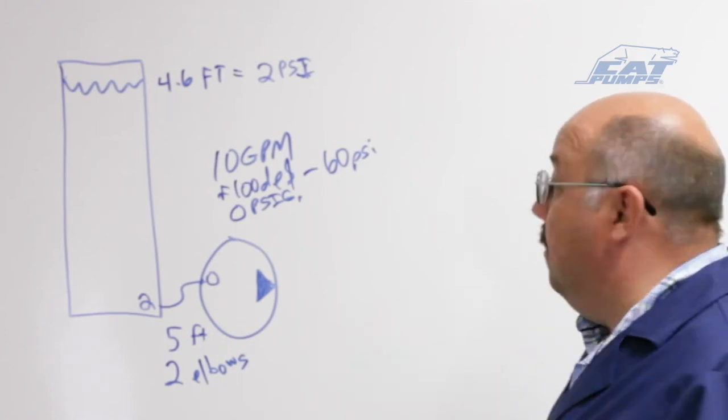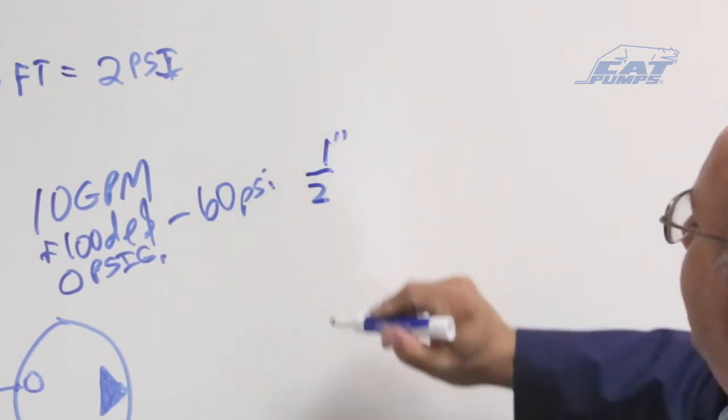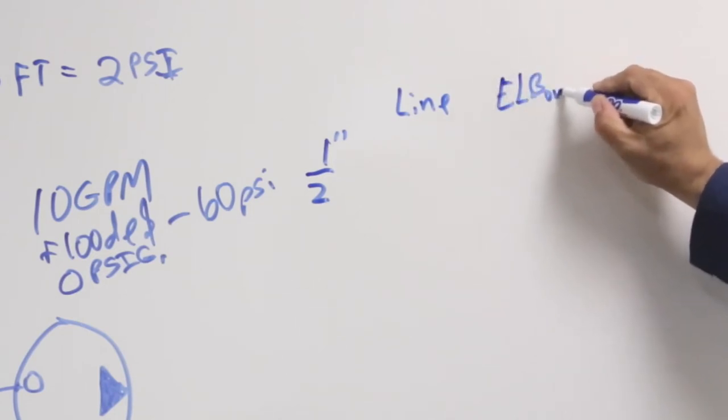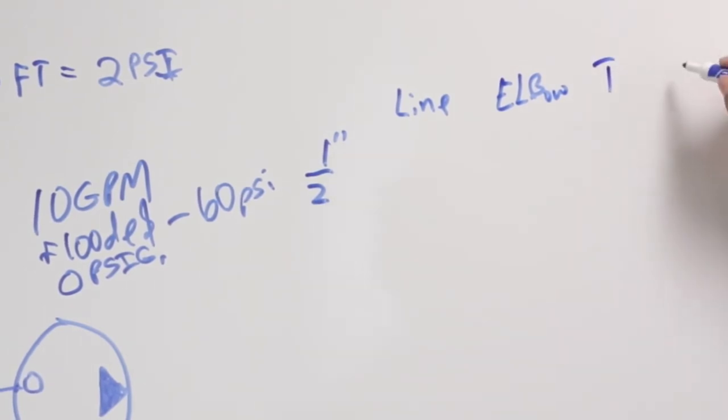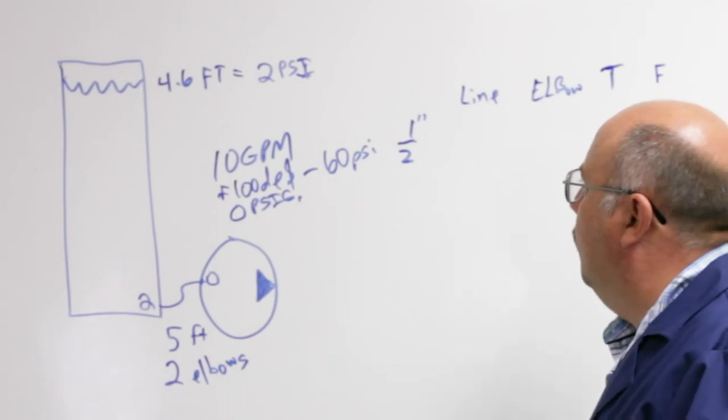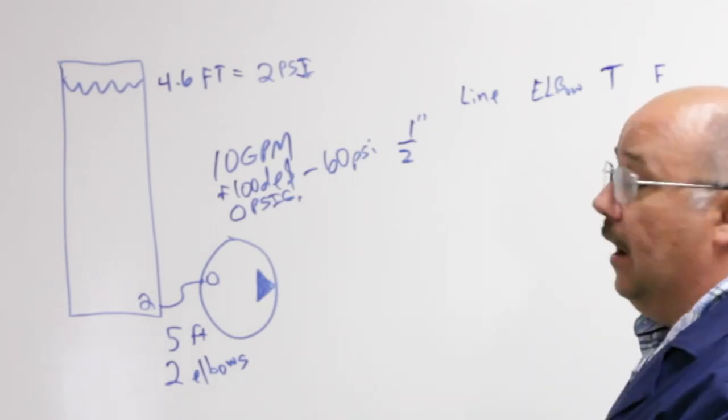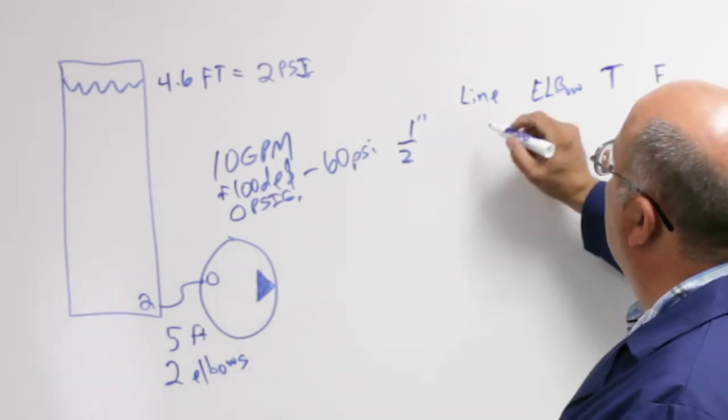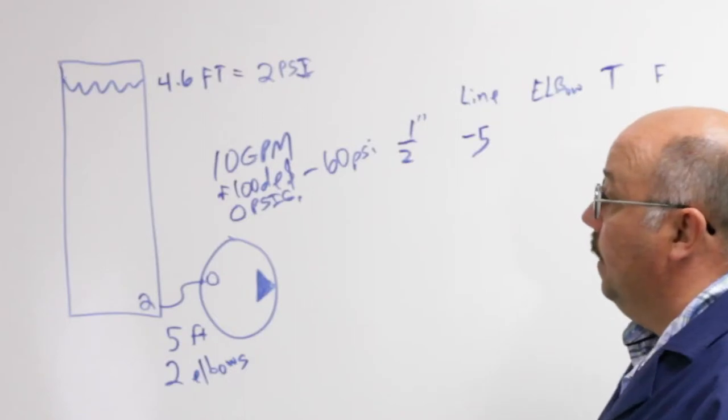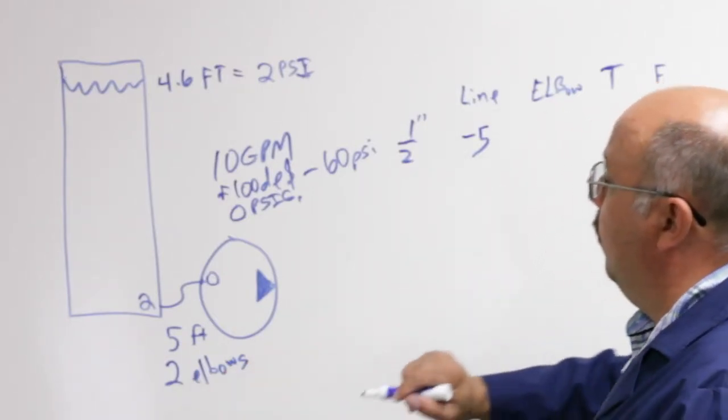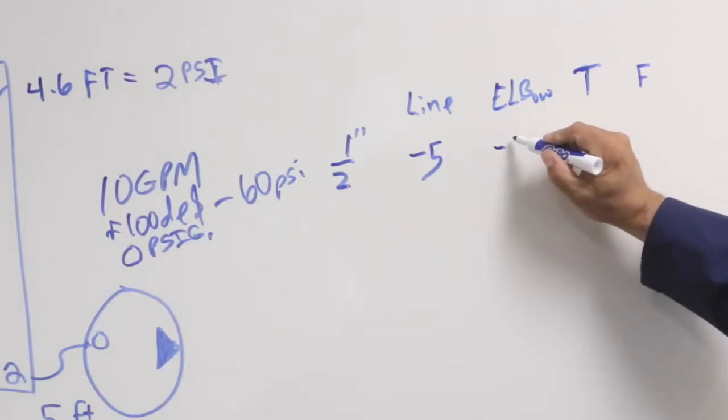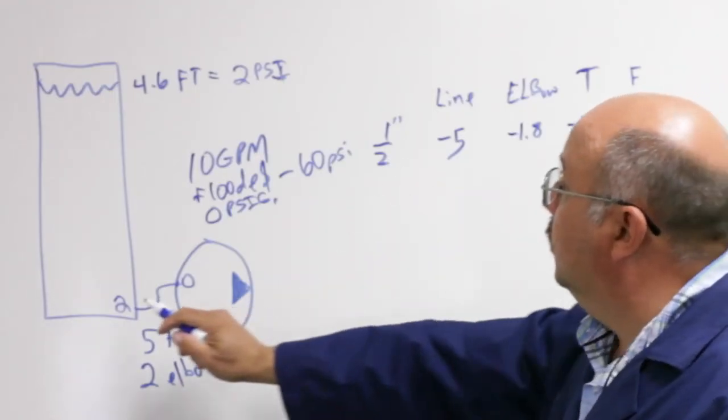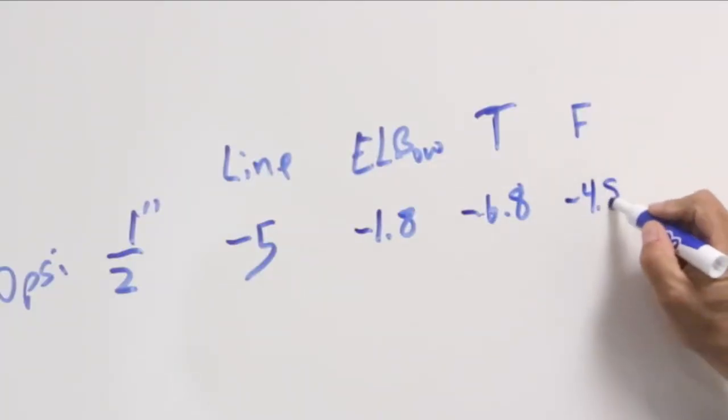Let's see, 10 GPM, maybe a half inch line will work. So we're going to look at a half inch line and we're going to account for the line loss. We're going to account for the elbows. Then we're going to add them up, get a total. And then we're going to get a final pressure. So if we look at charts and calculations that are available online or several places on the internet, we see that a 5 foot half inch line will drop minus 5 PSI at 10 GPM. A couple of elbows thrown in there. We find out that they drop another minus 1.8 for a total loss of minus 6.8. Therefore, our final pressure, 2 minus 6.8 is a negative 4.8 PSI.